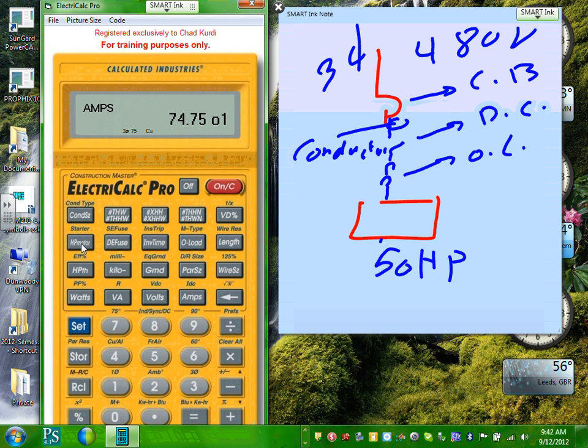Okay, what else do we have? Starter. Can you guys see where it says starter? NEMA starter. Hit set and go to the motor. You need NEMA starter 3. Does anybody know what the NEMA starter is? The size of the starters, right? Later, not this project, next project, when you guys size, you're going to be sizing NEMAs for me. I wouldn't accept anything other than NEMA. NEMA will get you the size of a contactor and the overload with it. So I need NEMA 3. Does that make sense? So from just the voltage and the horsepower, I got the NEMA starter, and I got the fuse or circuit breaker, and I got the overload.